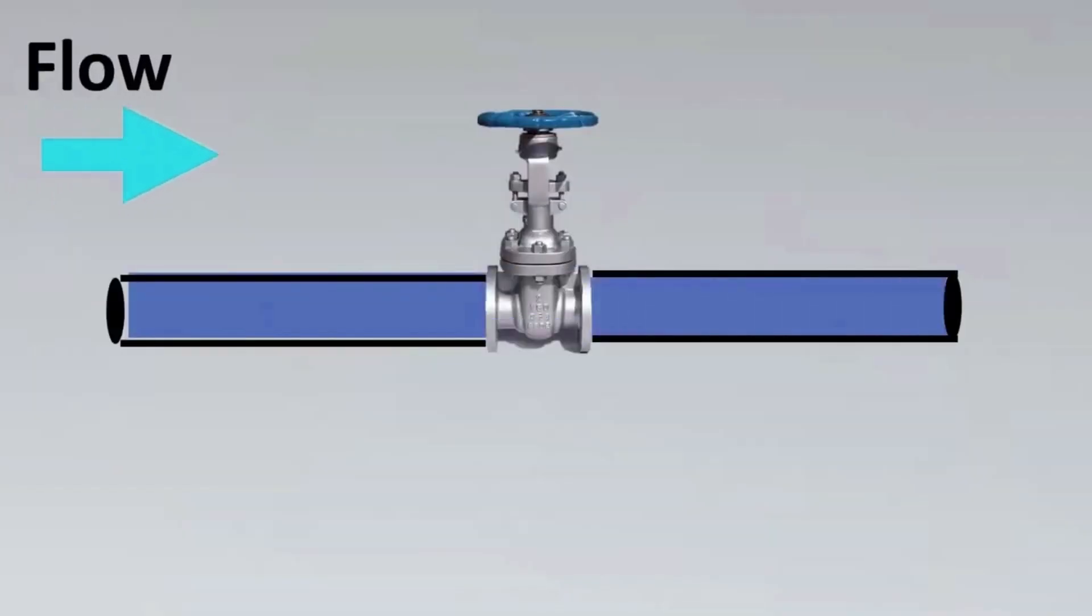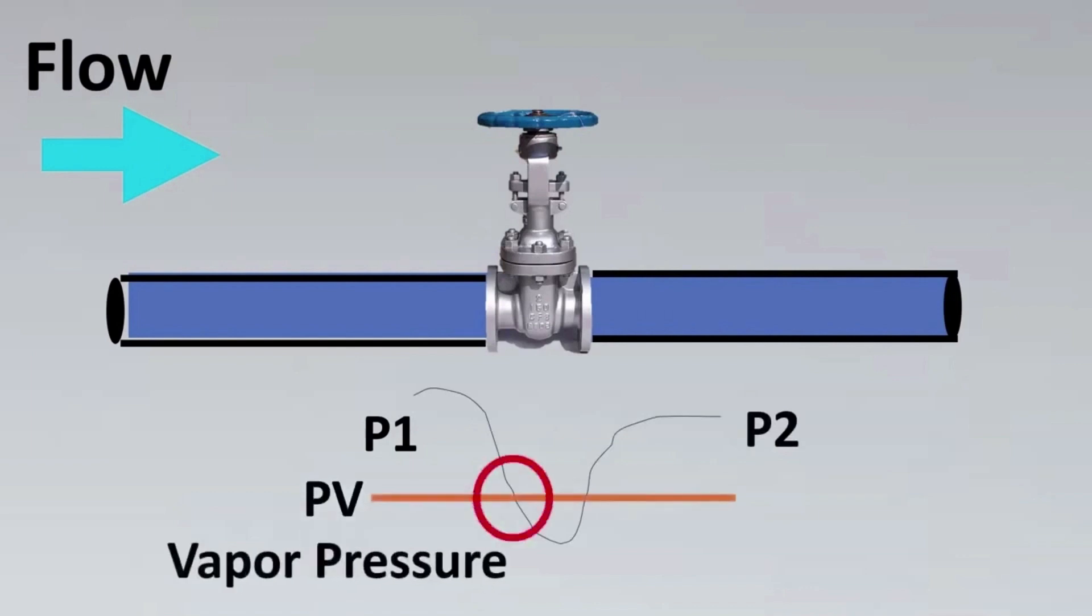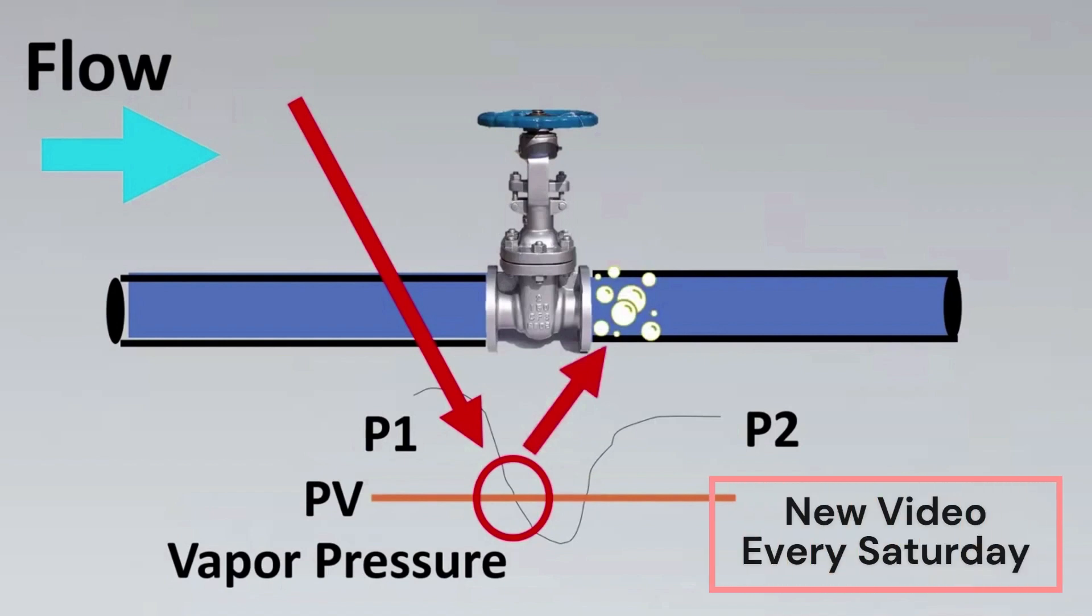Imagine this is your valve put in a line. With the flow, there is some restriction put, so you're going to have a DP or differential pressure created. The upstream pressure is P1 and the downstream pressure is P2. Imagine this is your vapor pressure curve. What happens when the fluid is at this particular region? The fluid is going to change from liquid state to vapor state.